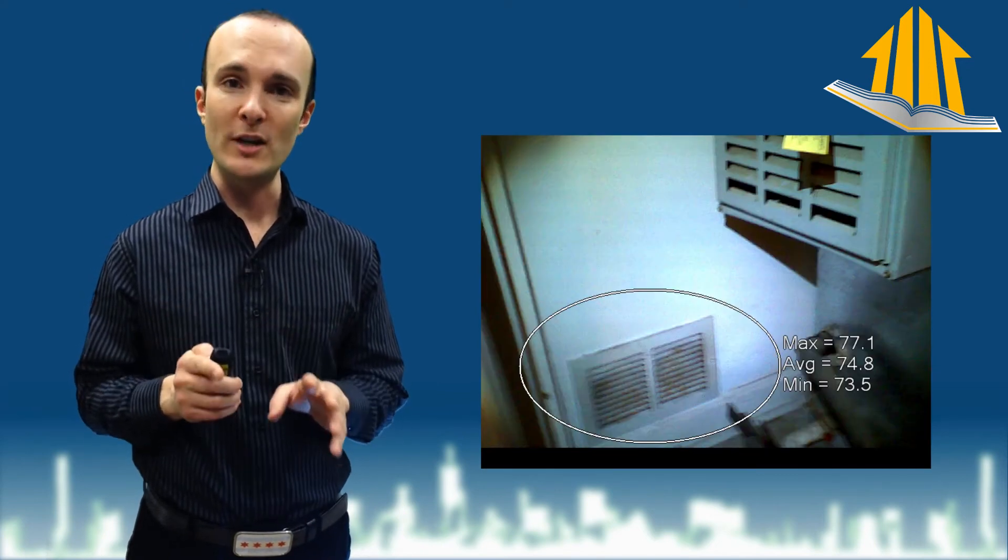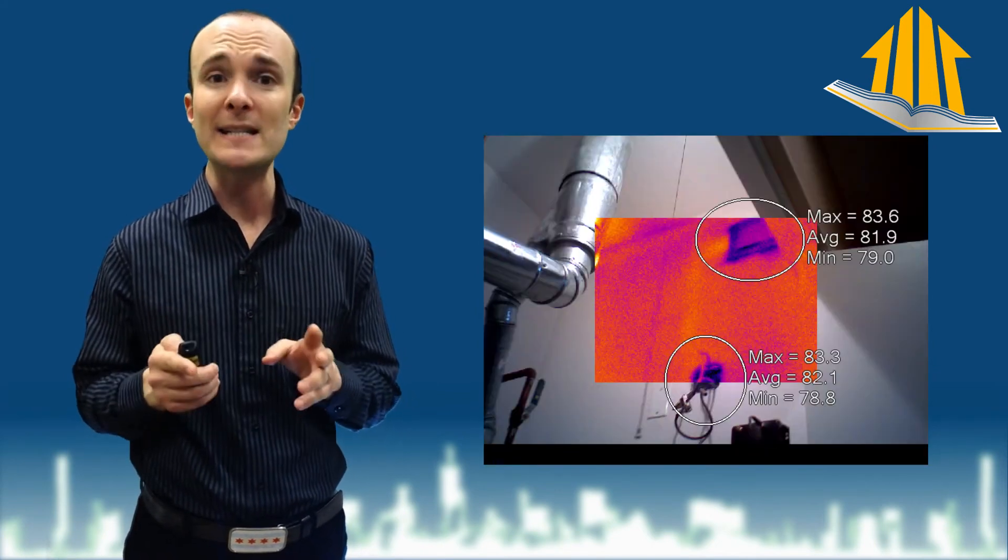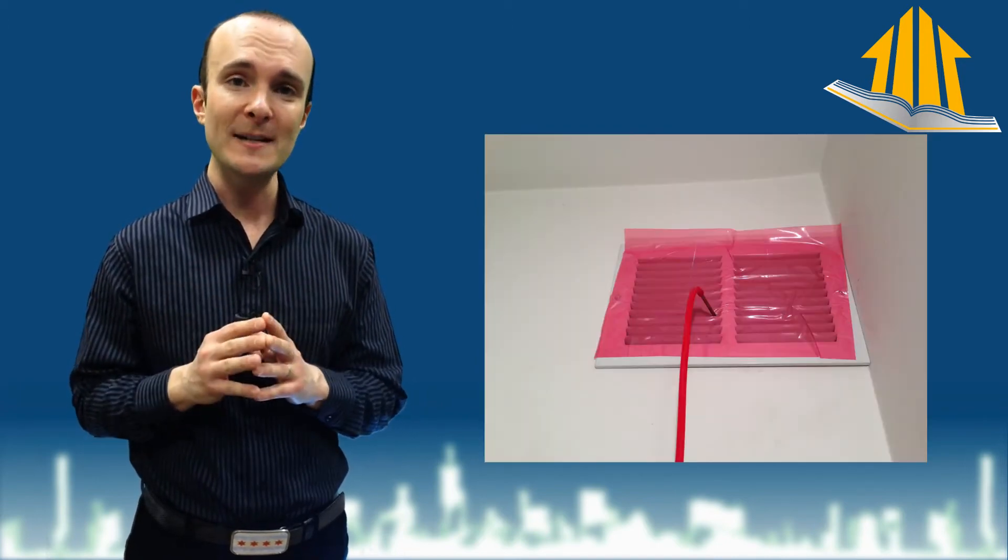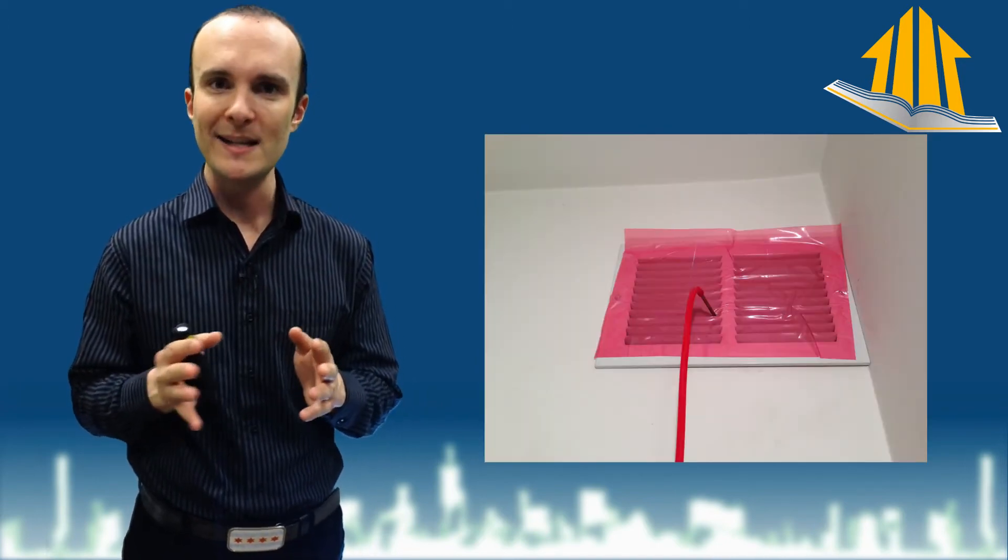We want to find out which one is which and what connects to the outside and what's basically causing more air leakage than we want between the two units. So we do what's called a zonal pressure test on each of those ducts that we suspect, and we can find out what is unnecessary.